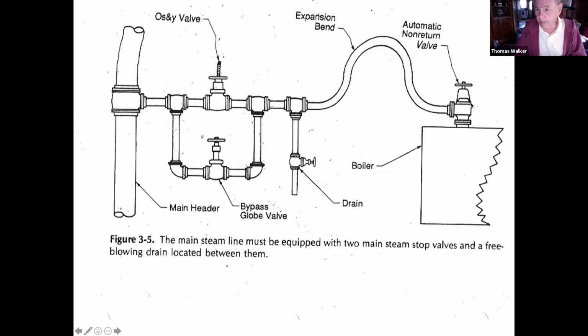Most arrangements will look something like this: a stop valve right at the boiler, a second between the boiler and the header, this being the main header. If it's equipped with the bypass, we already discussed the purpose of the bypass, right? That's to equalize the pressure across this valve and to pre-warm this section of the pipe. The free blow drain is pictured here. The definition of a free blow drain is that the end of the pipe is visible to us. It doesn't terminate below the floor level in a tank. We can see it.